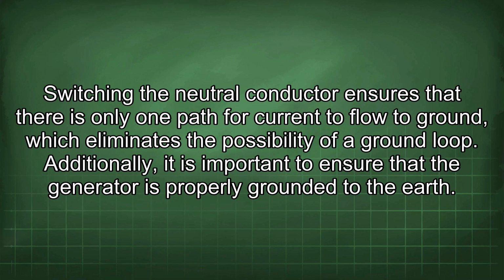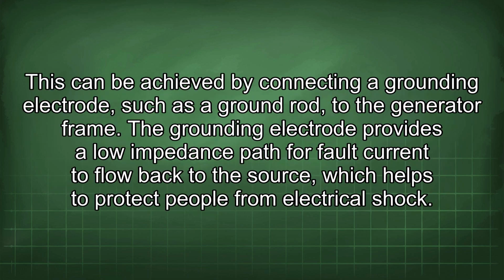Additionally, it is important to ensure that the generator is properly grounded to the earth. This can be achieved by connecting a grounding electrode, such as a ground rod, to the generator frame. The grounding electrode provides a low impedance path for fault current to flow back to the source, which helps to protect people from electrical shock.